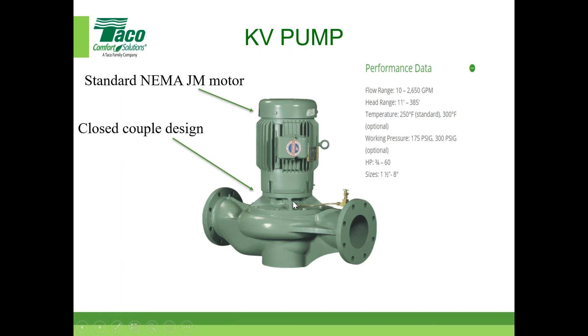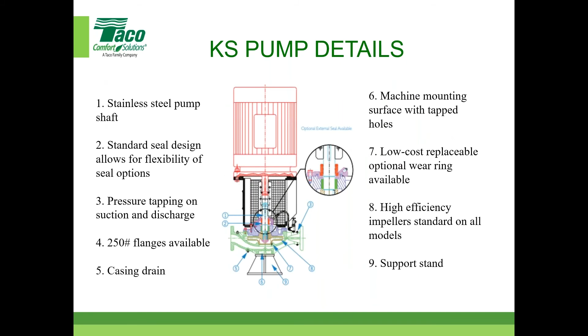Actually, a question, and maybe you already answered it, Brett, came up just before this group of slides, before the cutaway. And that was, can you mount the pump with the motor horizontally? Great question. I am going to cover that, but let's answer it since it came up already. The KV pump, that's this one, can be mounted horizontally up to 15 horsepower. Above 15 horsepower, the KV pump cannot be mounted horizontally, and the KS pump cannot be mounted horizontally at all. So hopefully that answered that question.